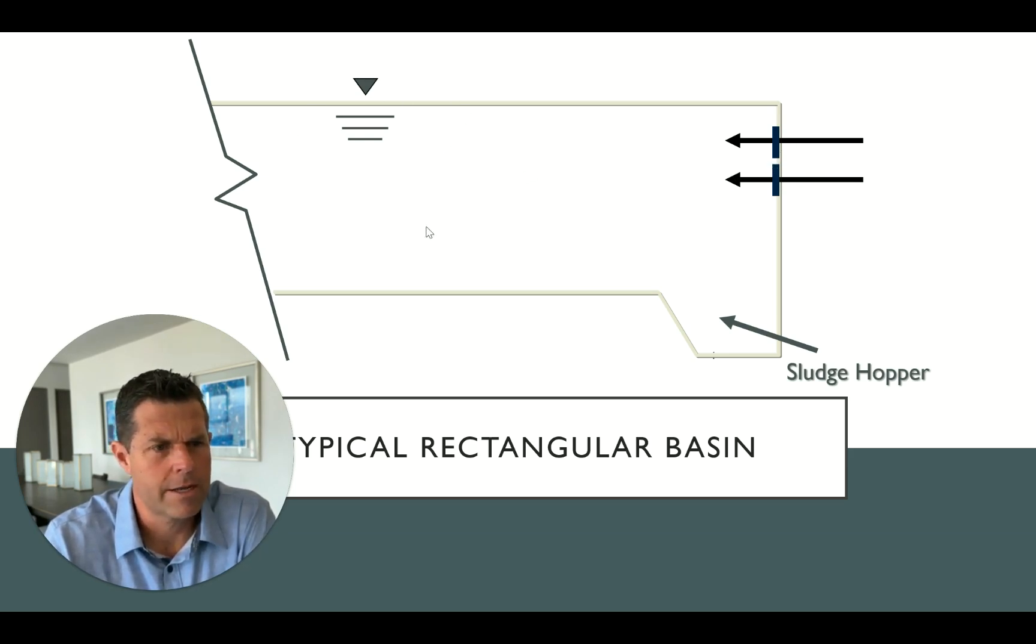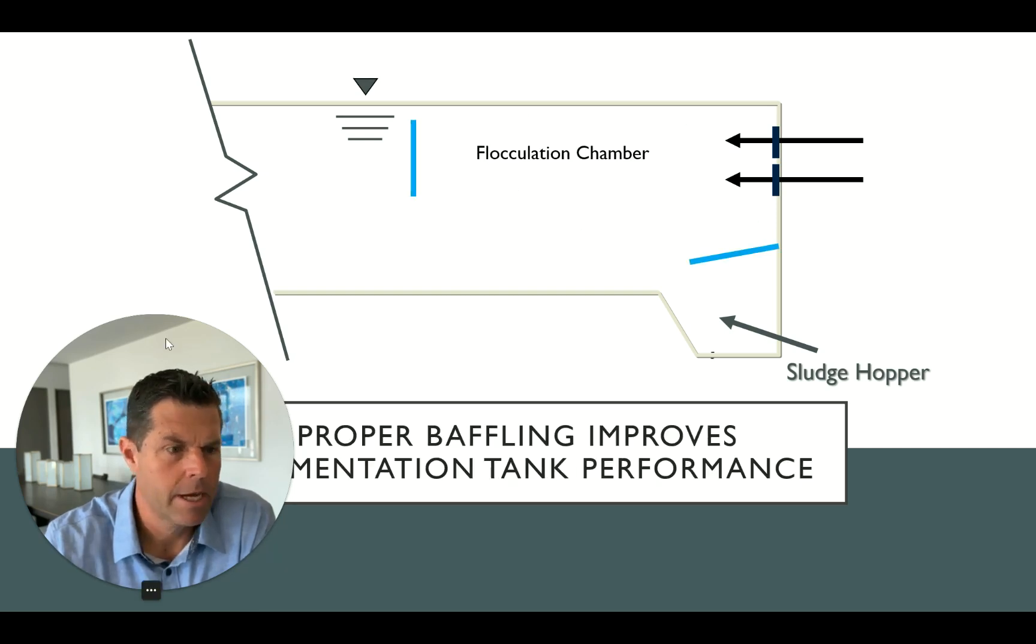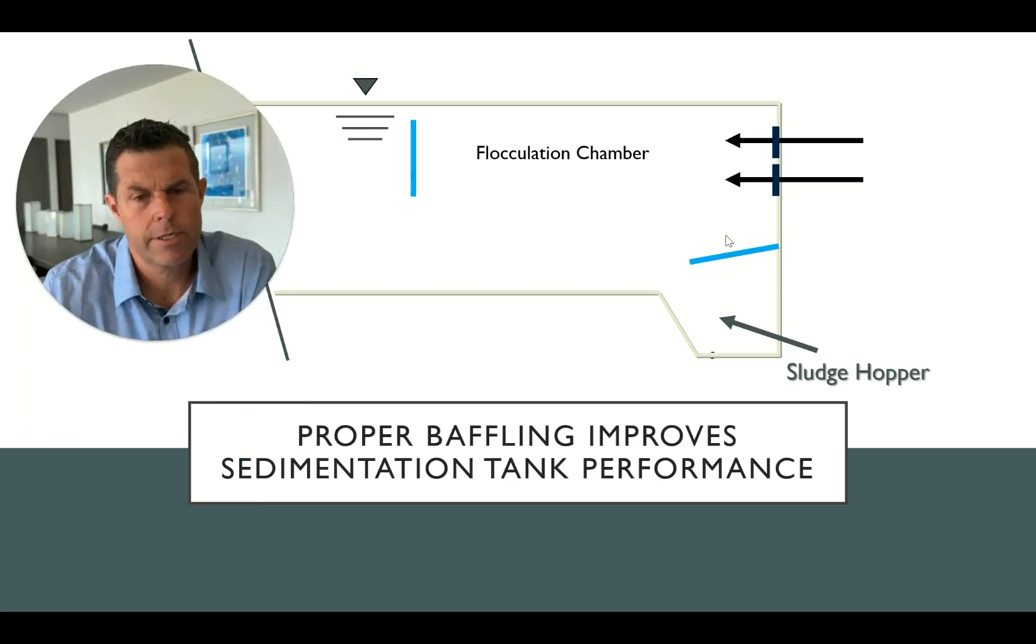I want to point out that, unlike a circular basin, there's no flocculation well. I think in the late 90s and early 2000s, our industry really took a step forward in paying a lot of attention to the design of flocculation wells. And even to this day, we don't see the analog in rectangular basins.